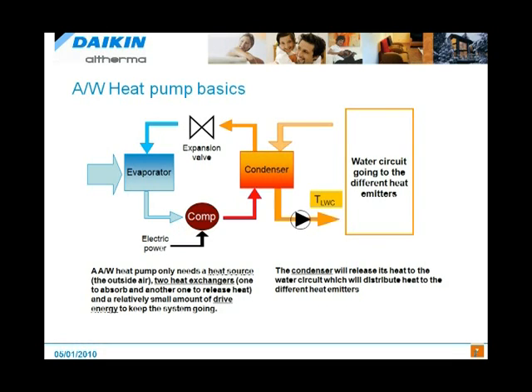So the technology has evolved tremendously since the 1970s and 80s, when we had heat pumps that could only manage to go down to 38 degrees ambient outside before going to electric strips. These are low ambient heat pumps that will work without electric strips down to -4 Fahrenheit with very reasonable COPs. We'll get into that.